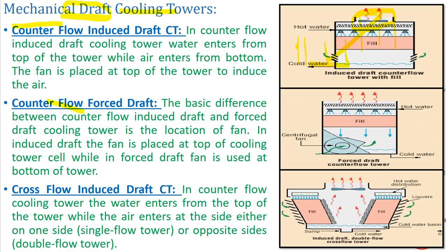The difference between induced draft and forced draft: in induced draft, the fan creates negative suction and takes air from inside, with air moving from bottom to top. In forced draft, the fan is relocated to the bottom of the cooling tower, forcing air inside. The air moves from bottom to top, while water still comes from top to bottom — a counter contact arrangement — but the fan is at the bottom, forcing the draft.